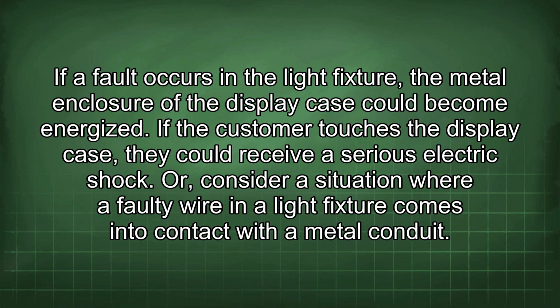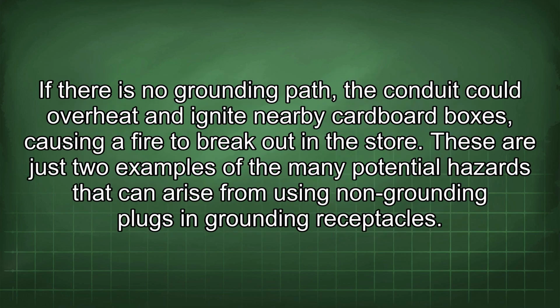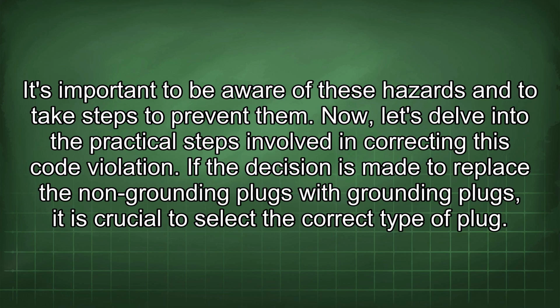Or consider a situation where a faulty wire in a light fixture comes into contact with a metal conduit. If there is no grounding path, the conduit could overheat and ignite nearby cardboard boxes, causing a fire to break out in the store. These are just two examples of the many potential hazards that can arise from using non-grounding plugs in grounding receptacles. It's important to be aware of these hazards and to take steps to prevent them. Now let's delve into the practical steps involved in correcting this code violation.